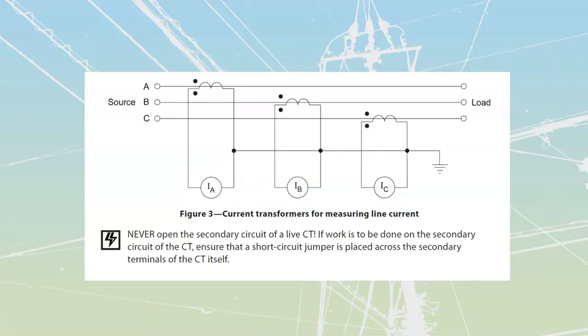All right, moving on past that, the next thing we're going to talk about is CTs. CTs are current transformers that are designed to, in most cases, clamp around the line or be bolted into the line, and then they're going to knock down the current into a smaller value. Now, because the current is going to a small value, that means the voltage is actually going to have to go to a large value. Remember that VA in is equal to VA out. So we do have a higher value of voltage across these things that you have to watch out for, but the current is always going to max out at 5 amps.